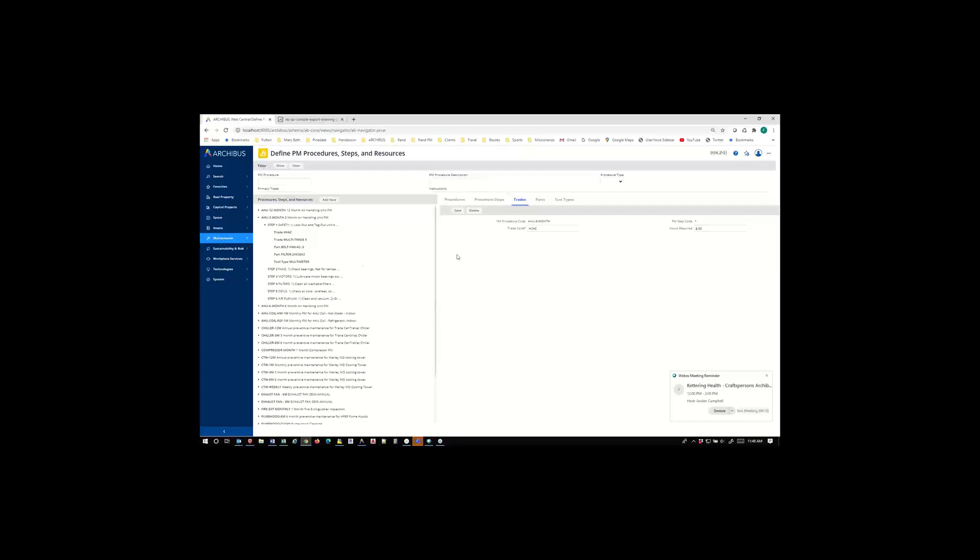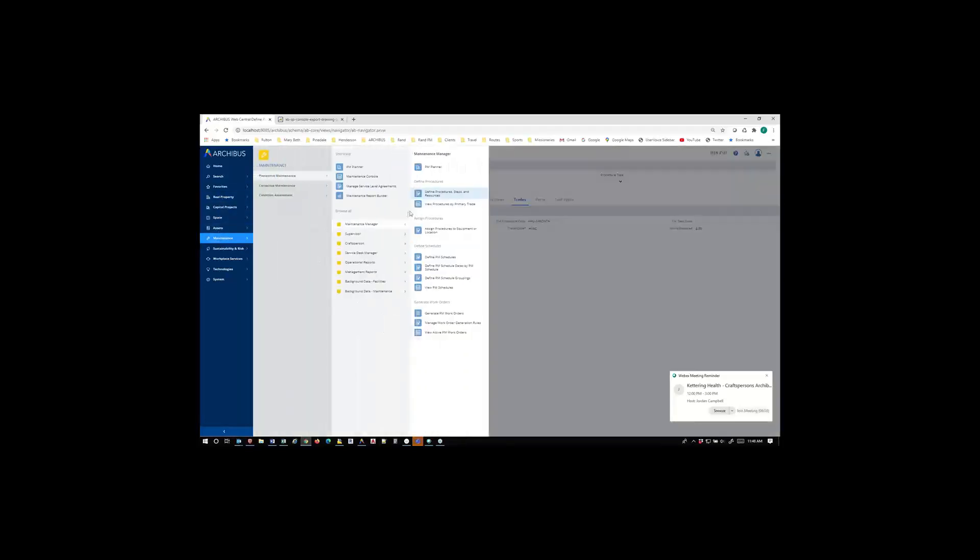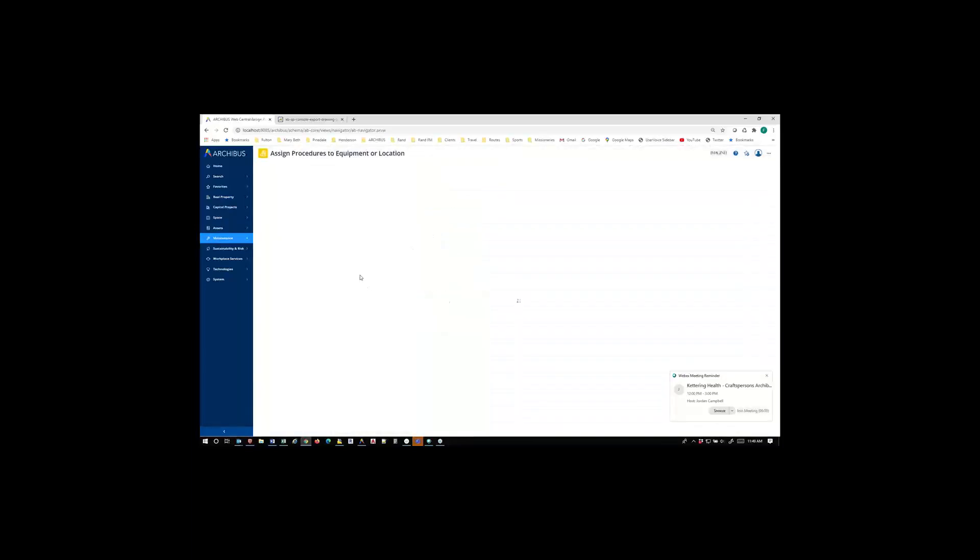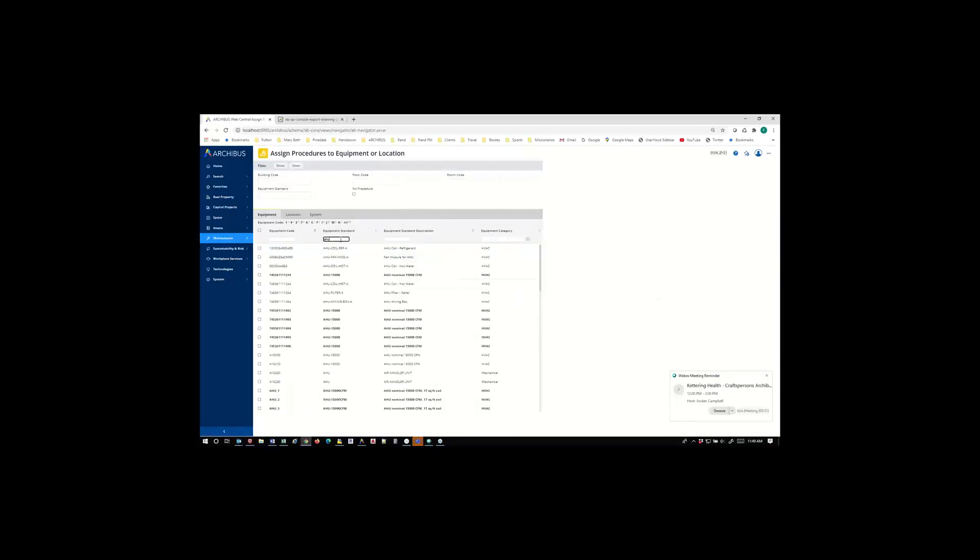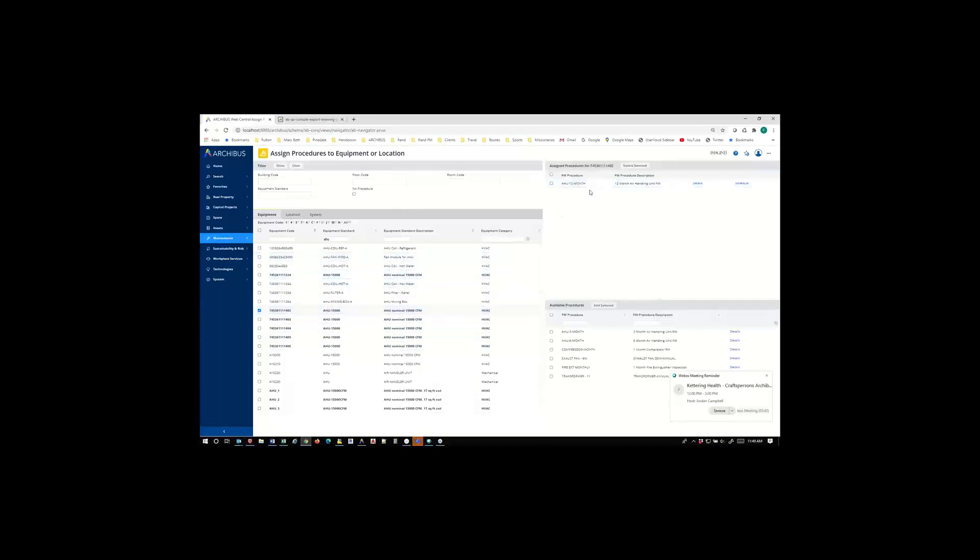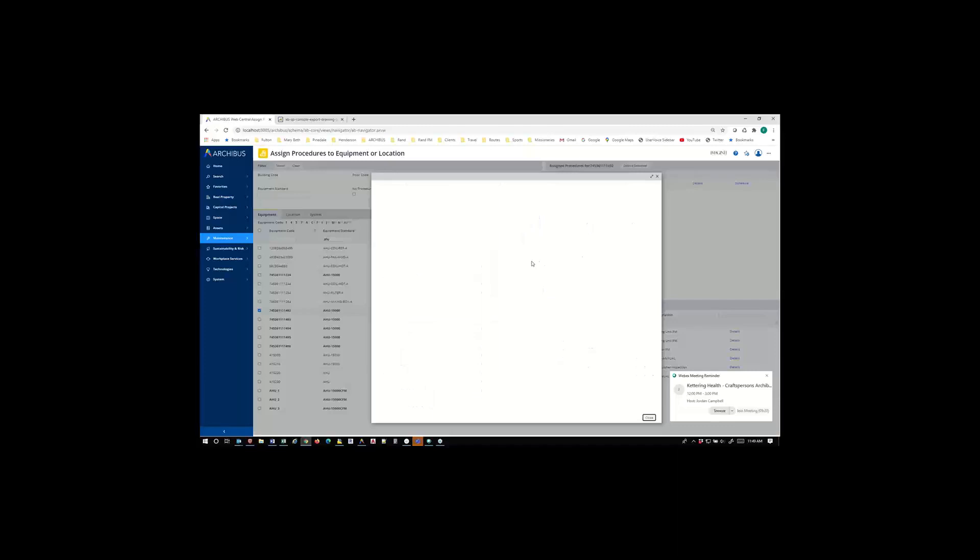Either way, you put in the information you need that you want somebody to do while they're in the field. And then you determine what resources are going to be needed and how many hours they would need to do this particular procedure. Any parts that they might need or tools can also be applied. So once you have that set of procedures established, then you can apply those to either equipment or to locations. Archibus has the ability to do PMs on particular rooms as well as on equipment. So in order to set that up, you assign the procedures to a piece of equipment. You can select a piece of equipment, I'm going to go to an air handling unit here, and you see some of them are bold and some are not. The bold ones have at least one assigned procedure to them.